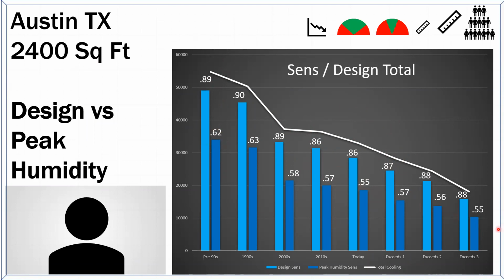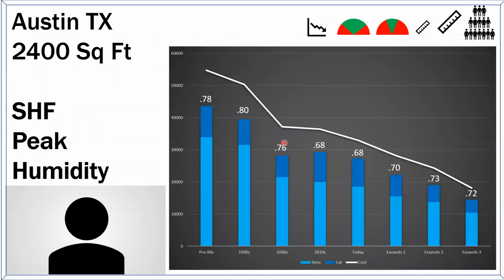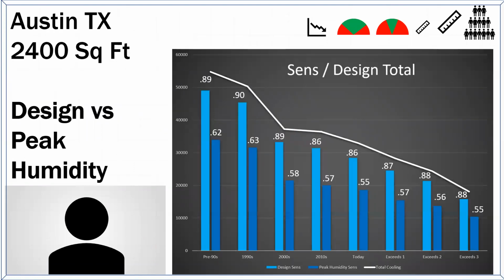Look at what it falls to now. It falls to almost half of what we actually need. The temperature control needs on that peak humidity day fall like a rock. So even though this tells me I have too much capacity, and it looks like a pretty big problem, what I really have is way too much capacity relative to the temperature control needs. It's a much bigger problem than we think. That air conditioner, on the most humid day of the year, when we'd hope it would run all the time, is going to run a little over half the time.